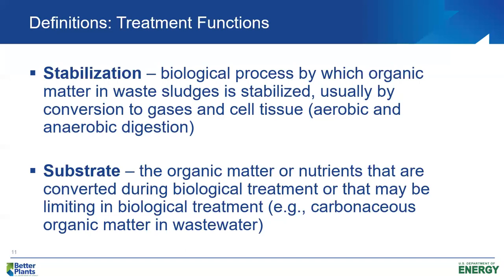Substrate is another term we need to be aware of. That's the organic matter nutrient that is going to be the limiting nutrient in the wastewater, and it will control the rate of the metabolic reaction. For instance, in most municipal wastewater treatment plants, the growth limiting substrate is biodegradable organic matter, carbonaceous BOD. Talking about nitrification, the growth limiting substrate there will be the ammonia nitrogen in the wastewater. So again, it's the critical substrate that's being used by the bacteria.